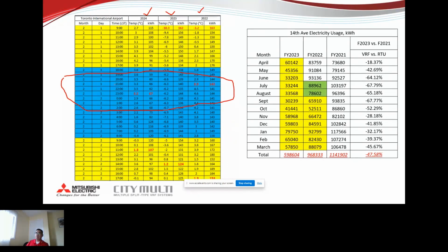At February 1st, 9 p.m., 3.3 degrees C outside, I'm looking at about 142 kilowatt hours of usage. Then at 3.2 degrees C outside, about 66 or 67 kilowatt hours. That's also in line with what we see, the COP is above 2, because at those times, really the majority of the energy consumption is most likely the heating.